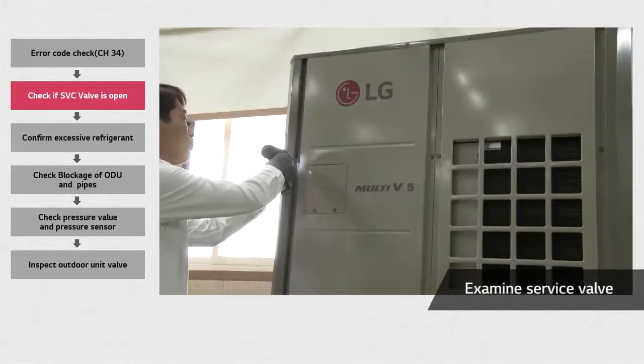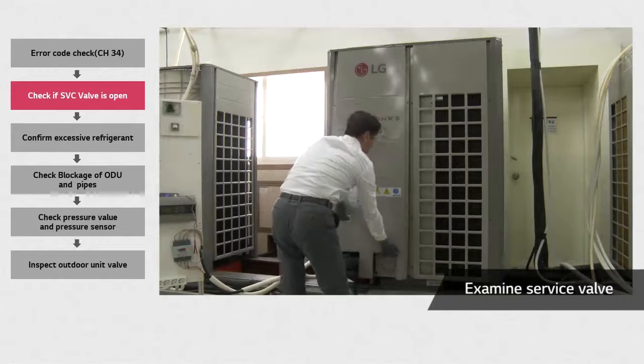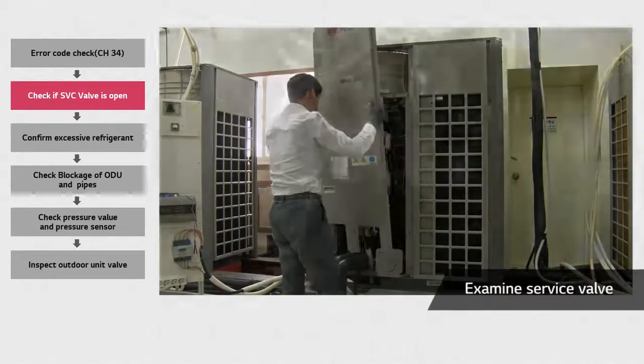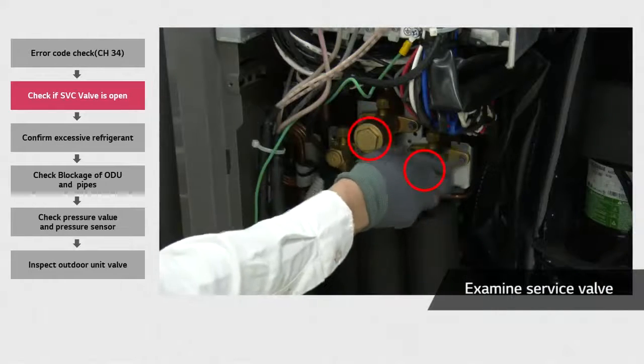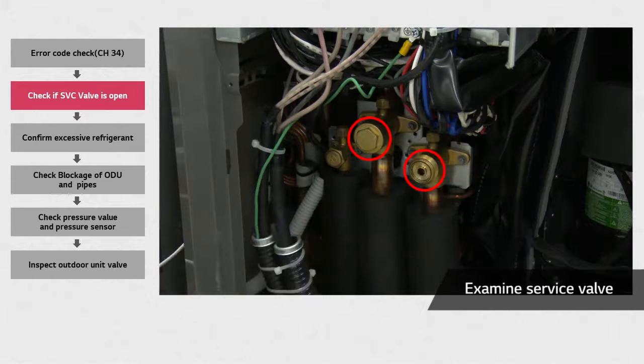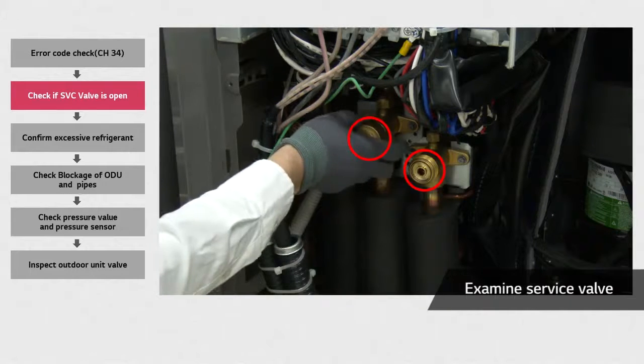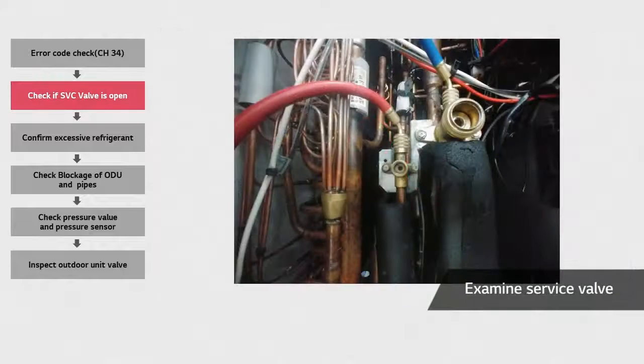To solve this error, start by removing the front panel of the outdoor unit. Remove the service valve cap to check if the valve is opened or closed. It should be opened. You can tell whether the valve is closed or open depending on the position of the top ring relative to the pipe. If the ring is about 2 centimeters inside the pipe, you can assume it to be closed. If it is almost parallel with the surface, the valve will be open.